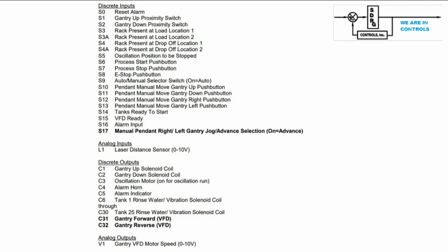As a result, thorough testing was required to catch small mistakes in coding and any of the various possible operational sequences. For example, the gantry speed was a single analog output but it used an output curve which included controlling the acceleration at start and deceleration at the stop point.